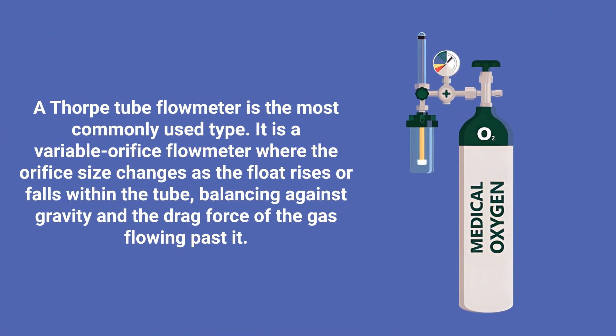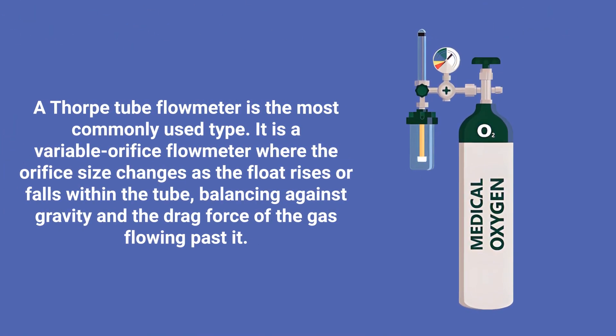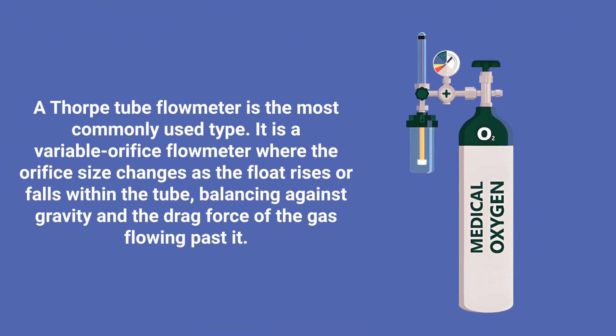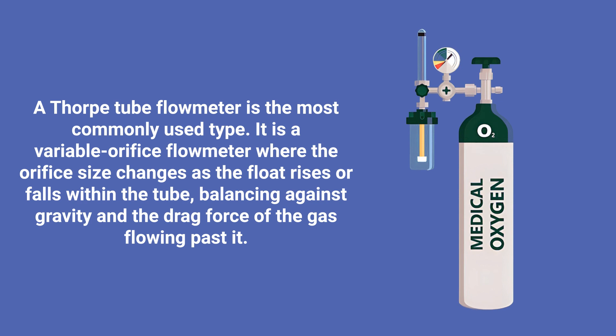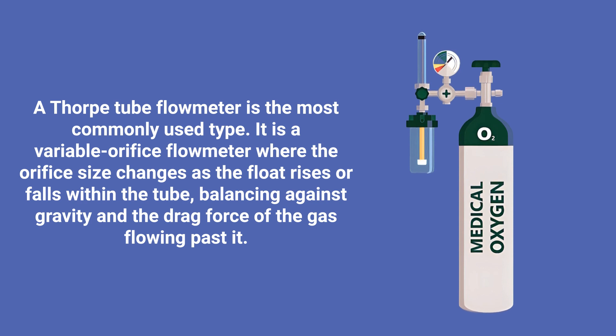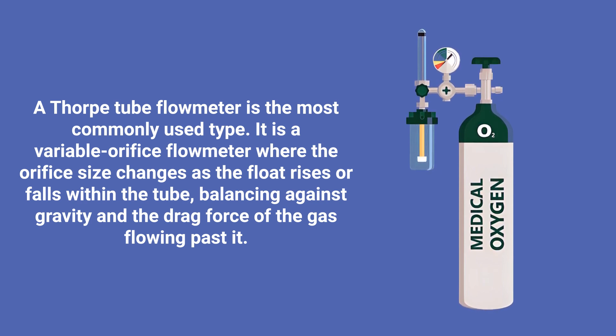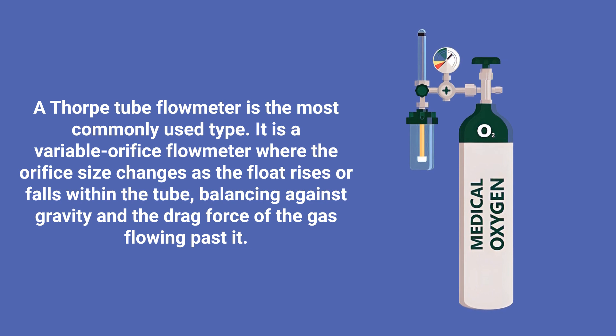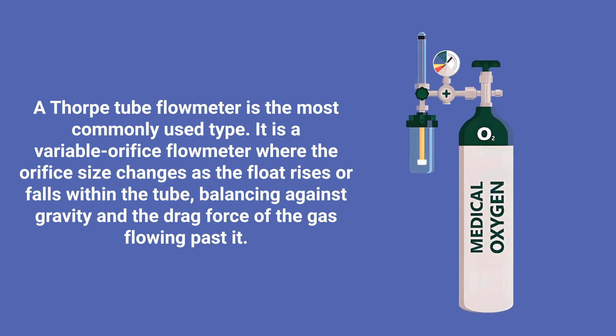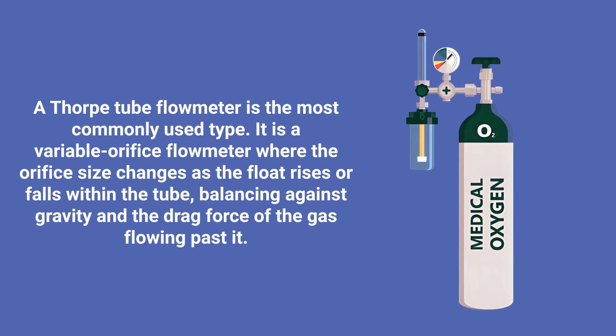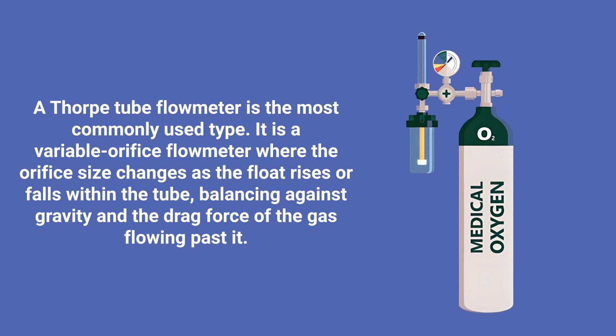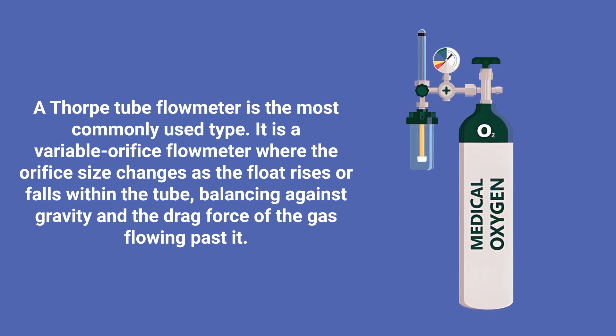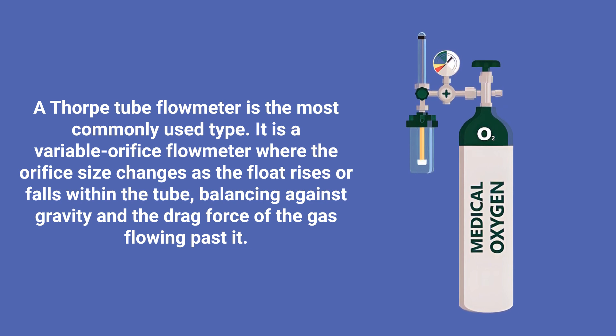A Thorpe tube flow meter is the most commonly used type. It is a variable orifice flow meter where the orifice size changes as the float rises or falls within the tube, balancing against gravity and the drag force of the gas flowing past it.